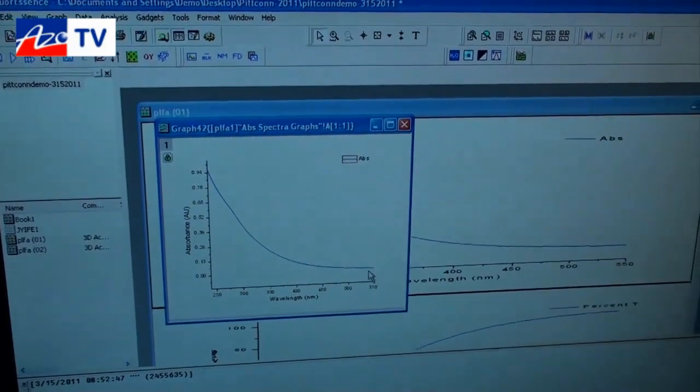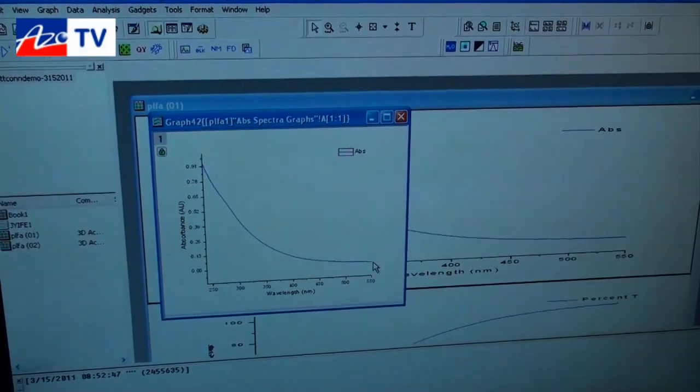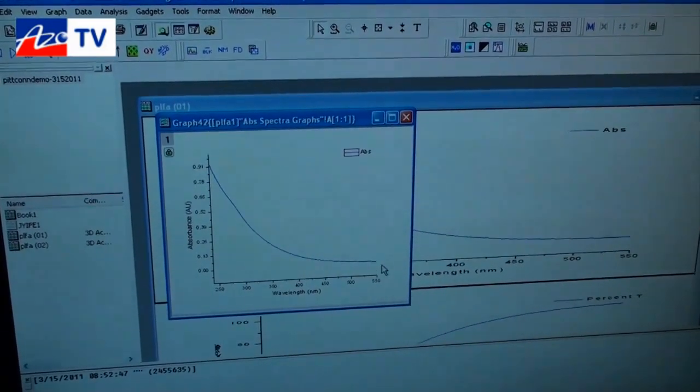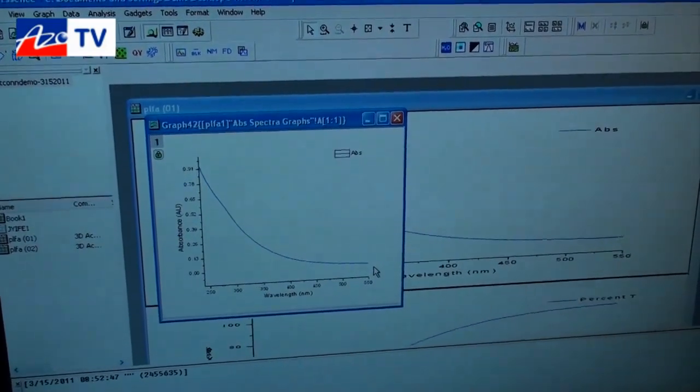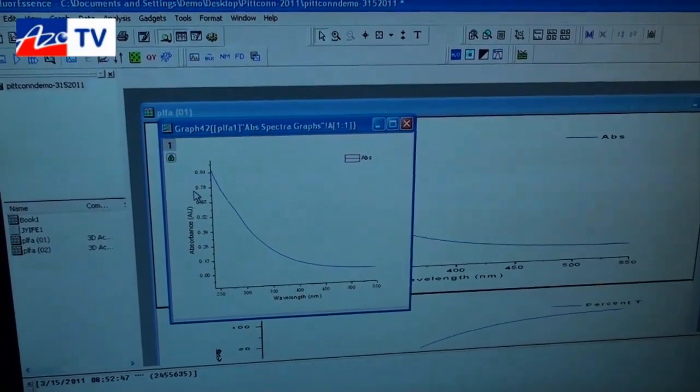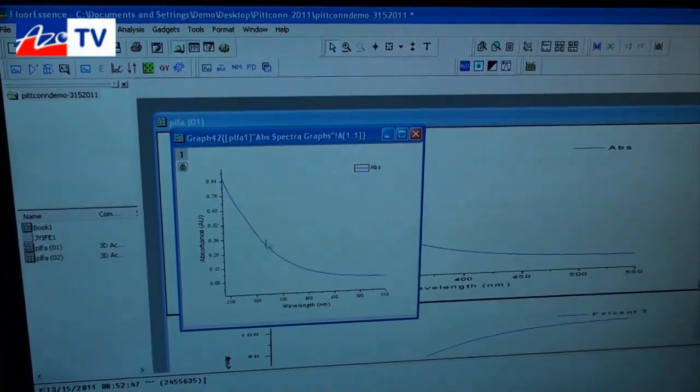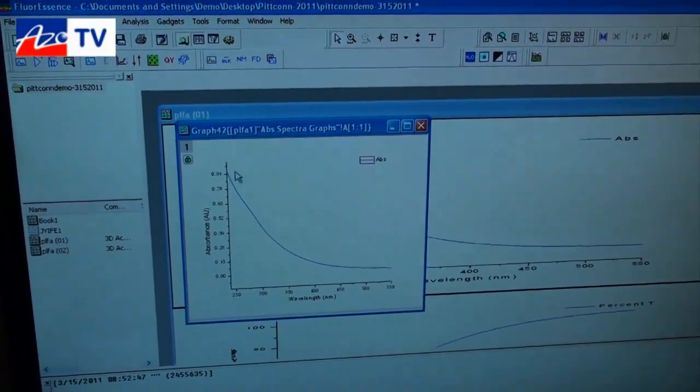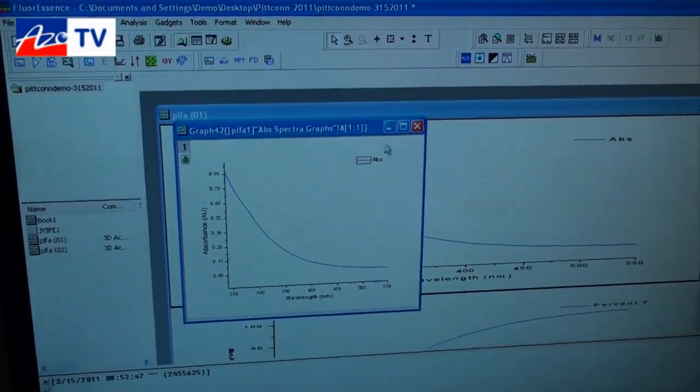One key thing about the instrument design is that it actually scans the excitation and absorption wavelength in reverse and this minimizes the exposure of the sample to the ultraviolet end of the spectrum. So as you scan in reverse you actually end up avoiding exposure to the UV light which can photo bleach the sample.